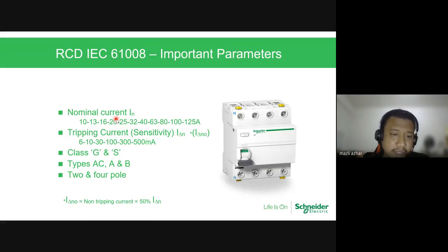All right. Then each of the RCCB must comply with the IΔn0, we call it non-tripping current, which is equal to 50% of the sensitivity. Why does this come into play? The reason is that when this RCCB connects to the load, some of the loads will have their own leakage, especially loads like LED. When you turn it on, they already have a leakage. So that's why the non-tripping current must come into play for every manufacturer, to ensure that it will not cause nuisance tripping to the whole system.